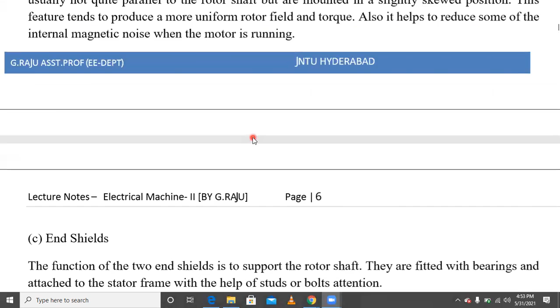So the rotor bars of this squirrel cage induction motor are short circuited by end rings at both ends of the rotor core. In large machines, these conductor bars and end rings are made up of copper, with the bars brazed or welded to the end rings. In small machines, the conductor bars and end rings are sometimes made of aluminum.